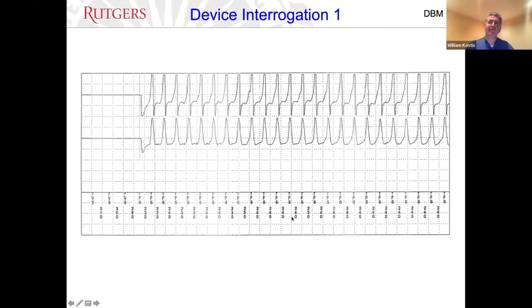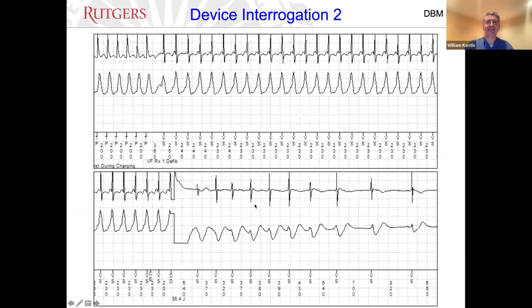This doesn't always work. Here's a similar VT in another patient. Here's anti-tachycardia pacing. Again, 8 pulses. It did not terminate the VT, though it didn't actually accelerate it in this case. Another round of ATP might have gotten a touch faster after that. And the way it was programmed for this patient, after 2 ATPs, if that wasn't enough in this rate zone, it was programmed to deliver a shock. Here's a high voltage shock, which then terminated the VT.